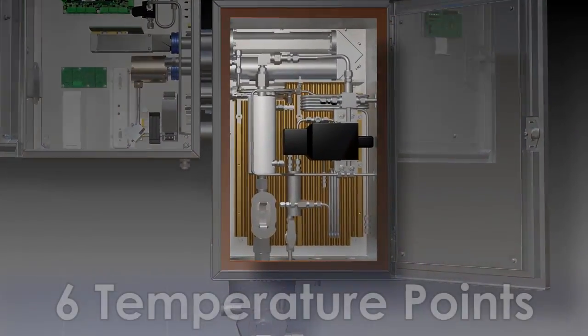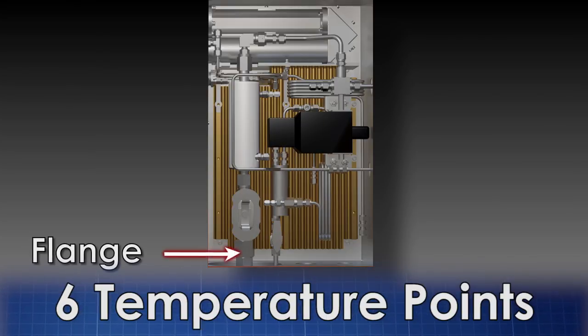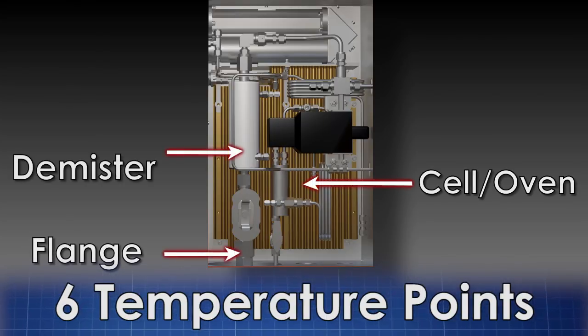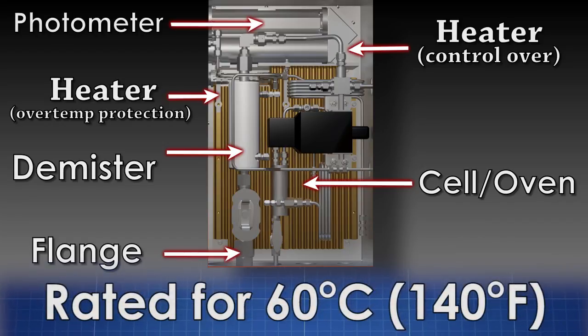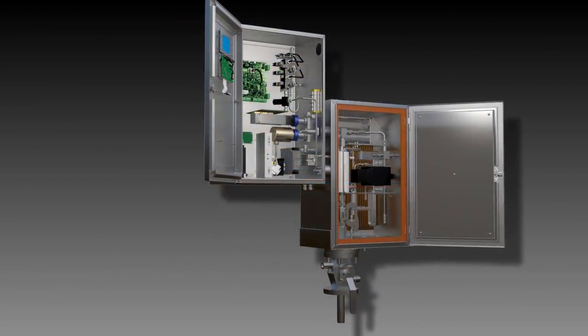The advanced thermal management reduces the electronics enclosure's internal temperature, extending the life of the electronics by 75%. The model 888 is also rated for ambient temperatures of 60 degrees Celsius, 140 Fahrenheit, without the need for external cooling.